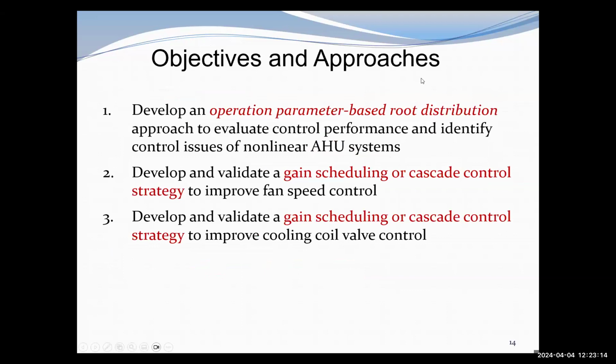So here come the objectives and approach. First, we would like to develop one approach to evaluate the control performance for nonlinear systems to help us identify the control issues. To achieve this, we proposed an operation parameter-based distribution approach. Then we want to develop the gain scheduling or cascade control strategies and validate their improvement for the fan speed control and cooling coil valve control.